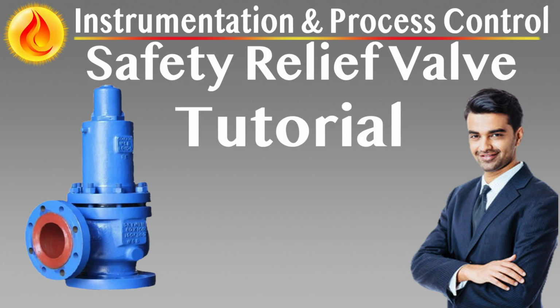Pilot-operated relief valves are advanced pressure relief devices that use a separate pilot valve to control the opening of the main valve. Unlike direct-acting spring-loaded valves, the main valve in a PORV remains closed under system pressure and opens only when the pilot valve vents the dome, the space above the main piston or diaphragm. This design allows for higher set pressure stability, minimal leakage, and superior back pressure tolerance, making PORVs ideal for high pressure, high capacity, and tight margin operations in clean services.